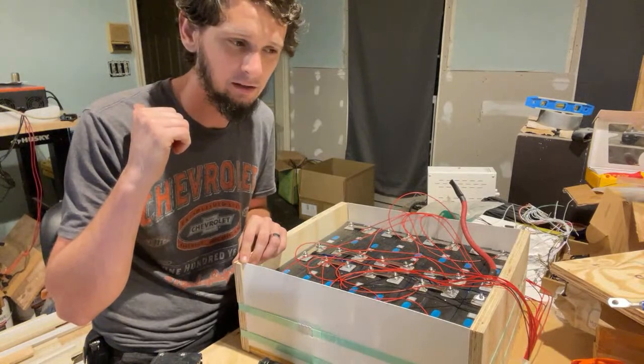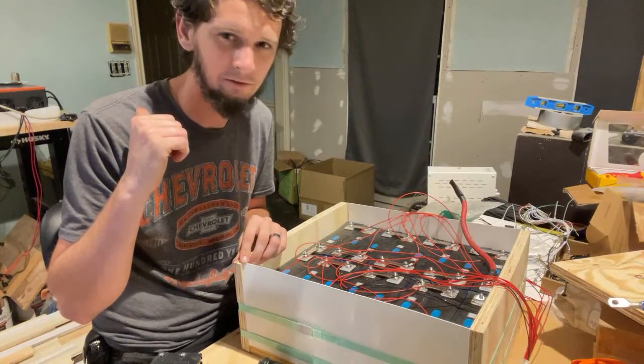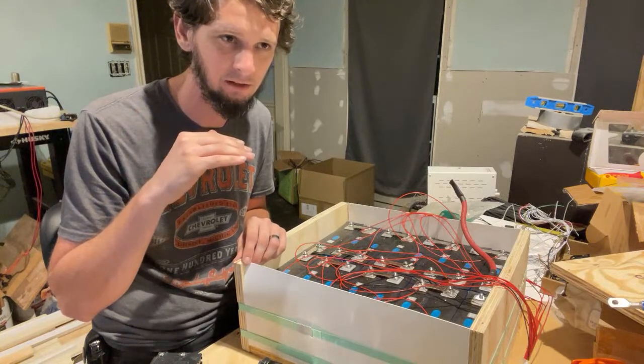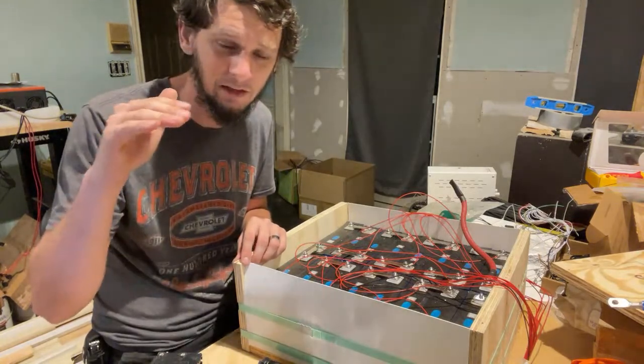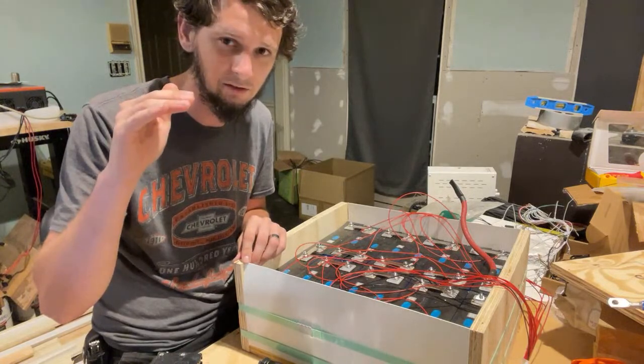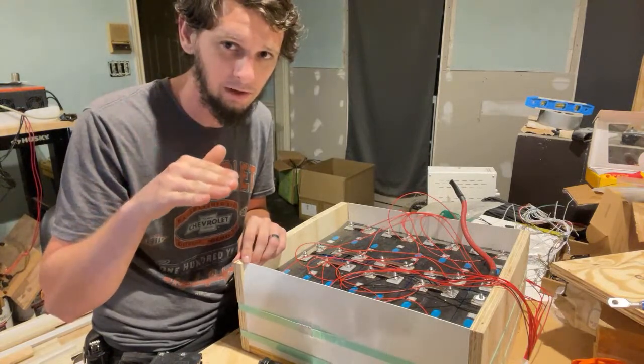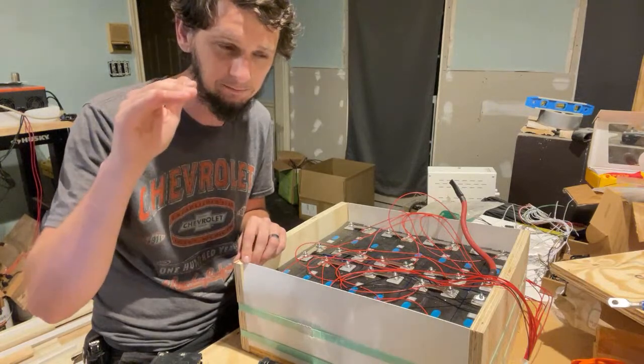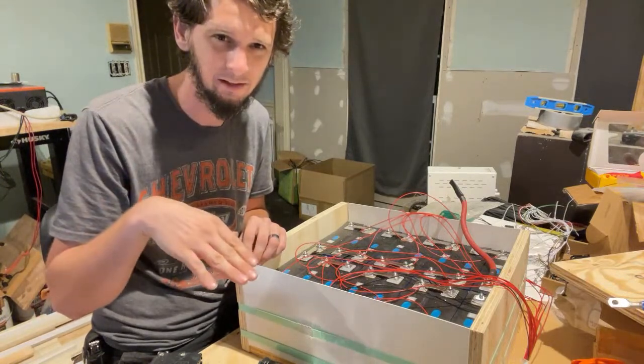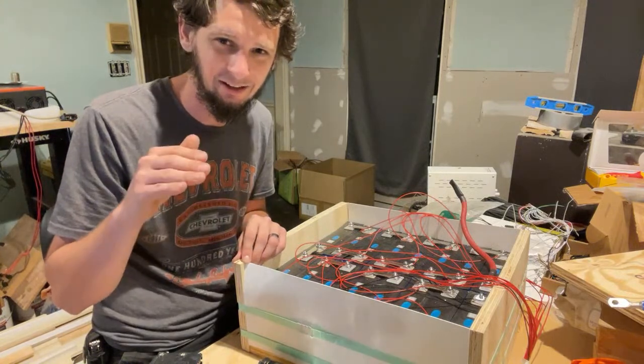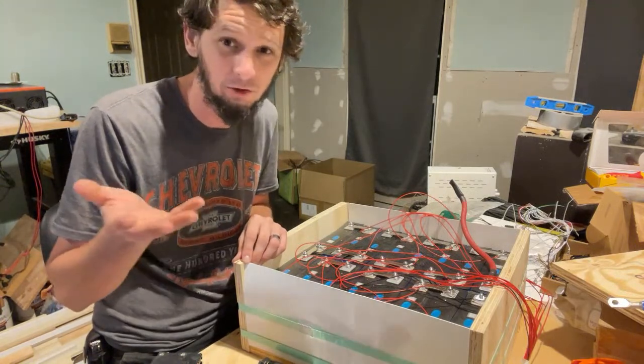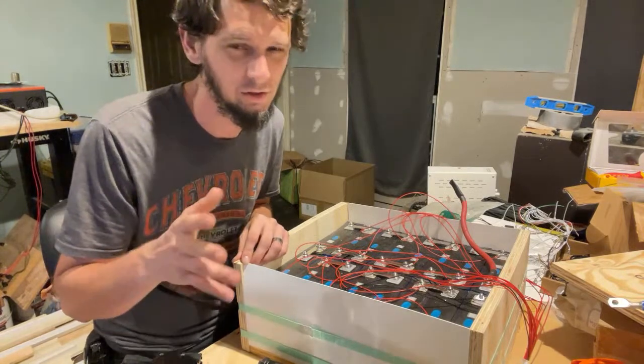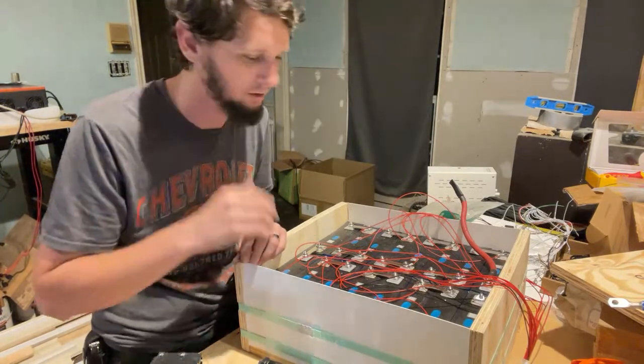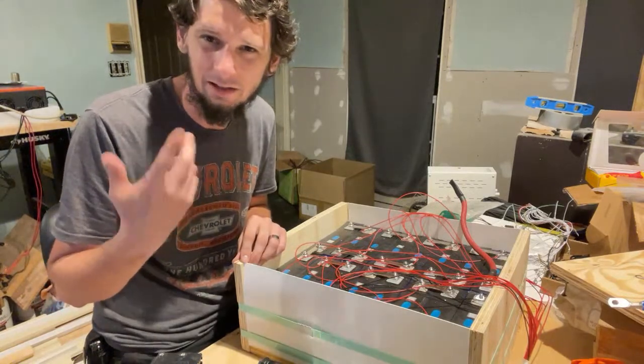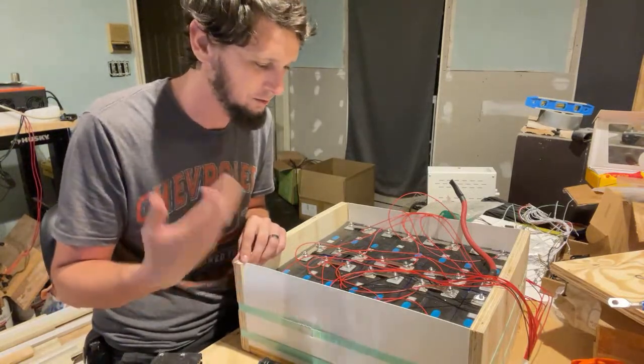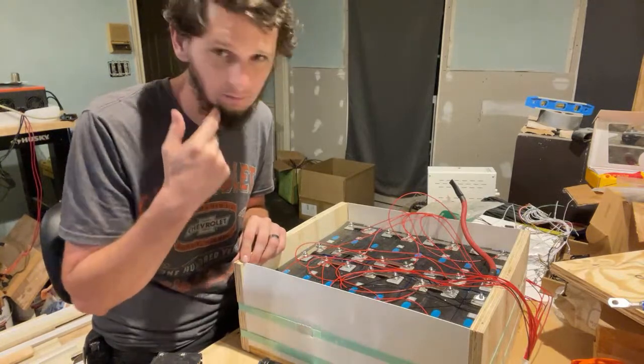With this one, I think it's like 54 or 52 volts. So if I've got the charge voltage set to 57, as soon as it hits 57 it stops charging, drops all the way down to like 52 volts, and then starts charging again. That seems silly to me, because 52 is usually below nominal charged voltage—around 51.2—but it seemed to rest higher than that. So it could be something I'm doing wrong or thinking about wrong, but I was trying to contact them and work through this, and they don't usually listen to me.